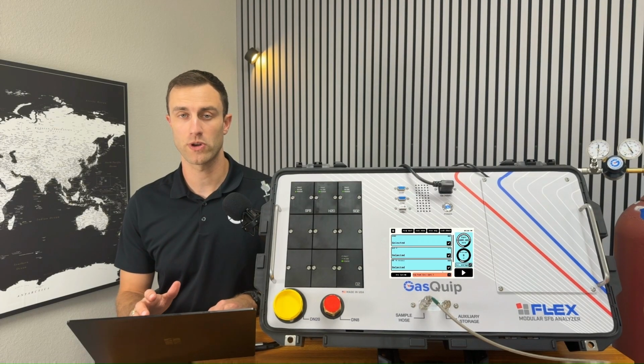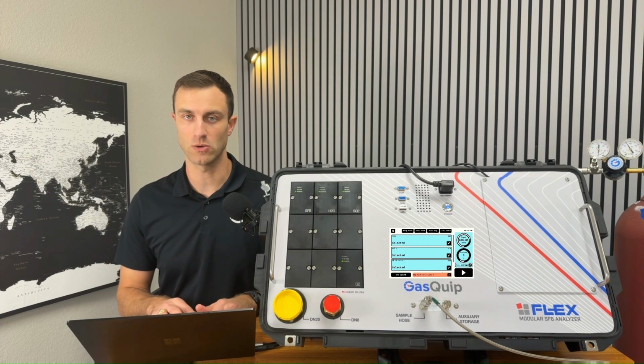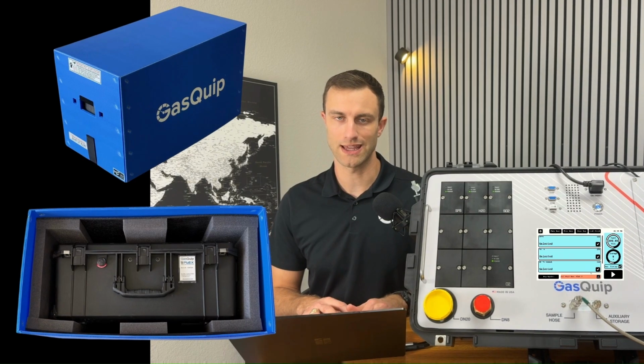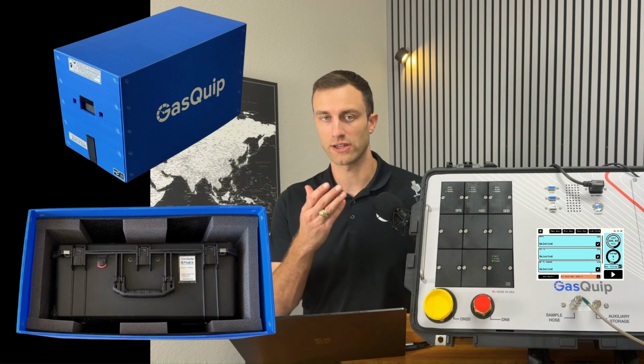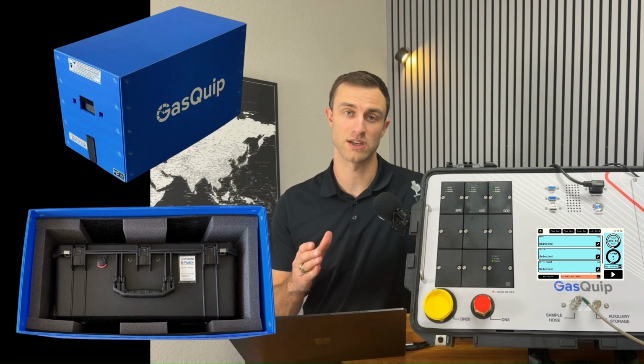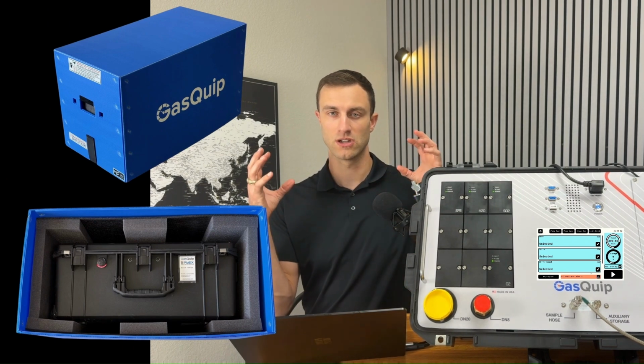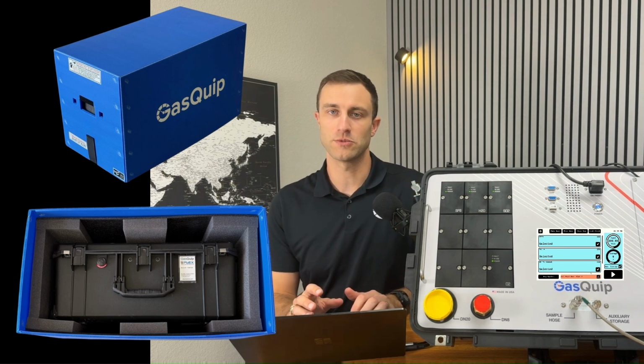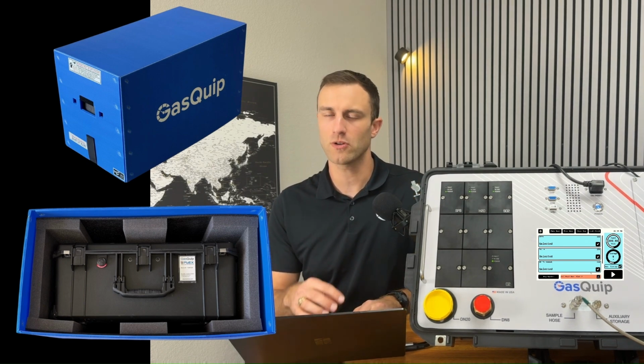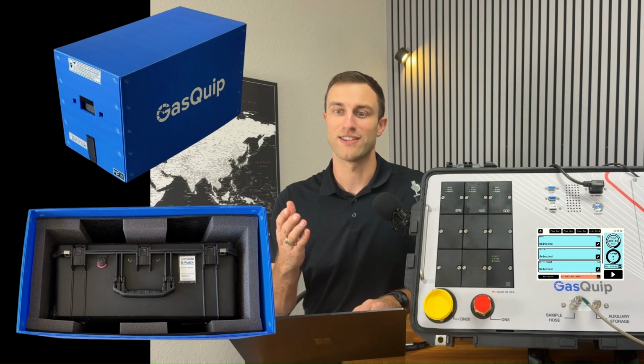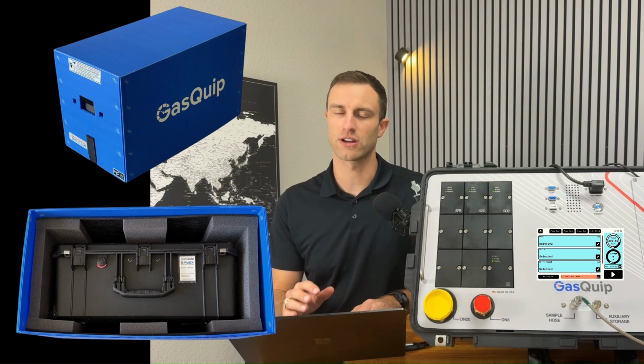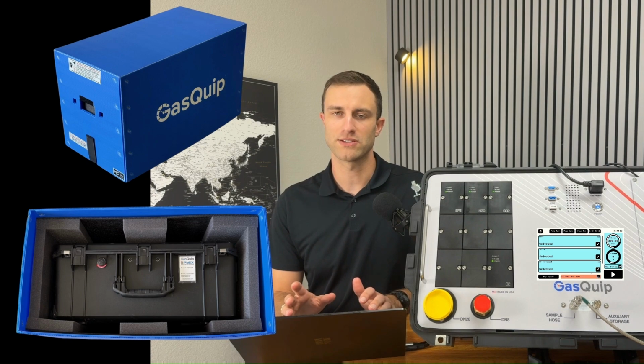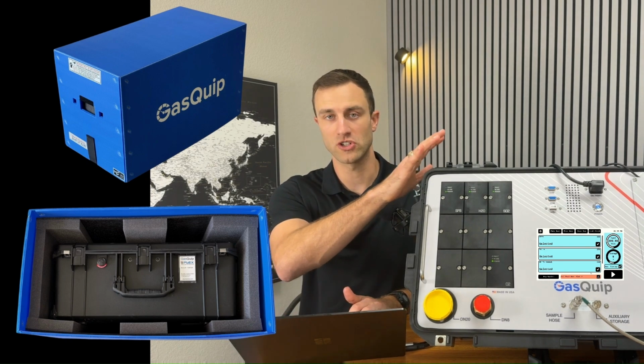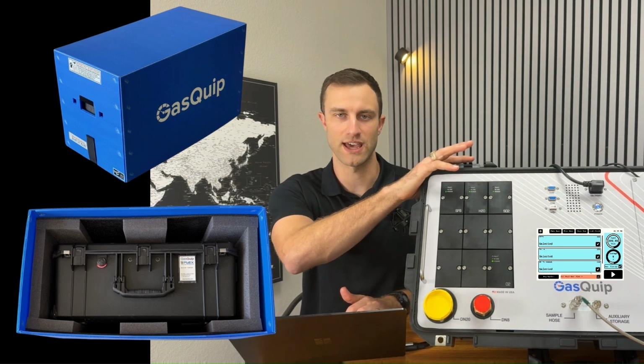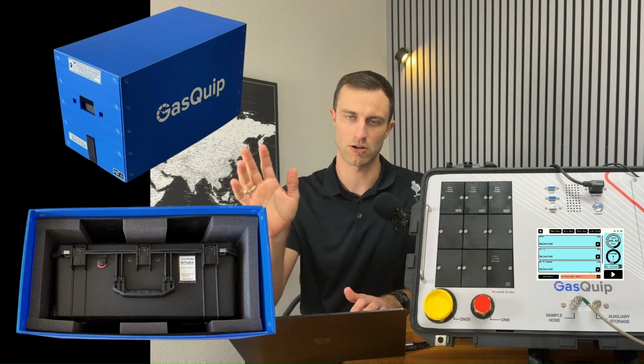If you're going to be transporting or shipping your analyzer anywhere, especially using UPS or FedEx, you always want to put it in a protective box, either like the one that we sell or the cardboard box it comes in with the clamshell foam pieces. Anytime you ship the analyzer or any test equipment, you should know that UPS, FedEx, DHL, they're going to beat the snot out of it and basically break anything that you ship. So never just send the analyzer by itself in its case. They will damage it.